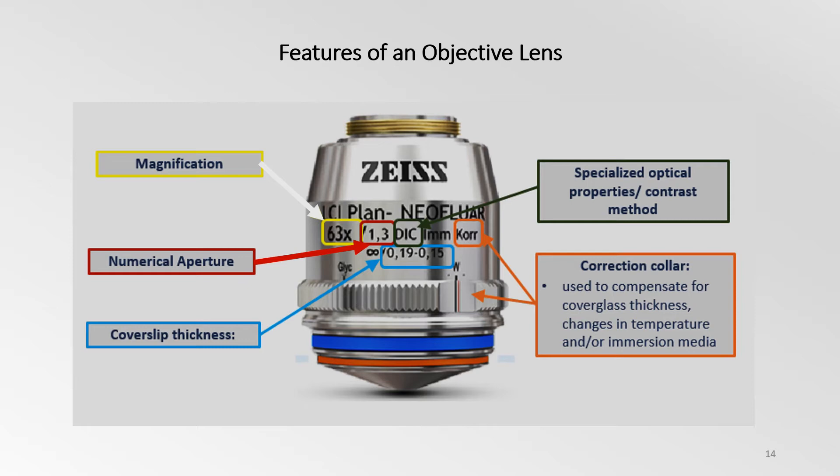Most objectives are designed to image specimens that are covered by a cover glass or coverslip. The value inscribed on an objective indicates the thickness of these coverslips. Since there may often be small variations in thicknesses within a batch of coverslips, some objectives have a correction collar that adjusts the placement of the objective's internal lens elements in order to compensate for these variations. Some of these collar adjustments can also correct for changes in temperature or immersion media. Additional contrast enhancing properties of the objective are also inscribed on the objective barrel.